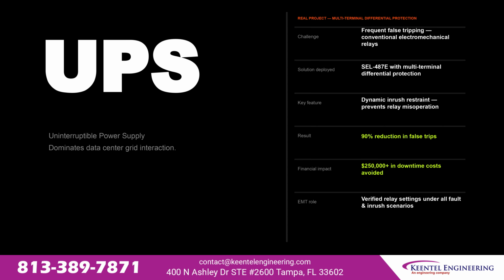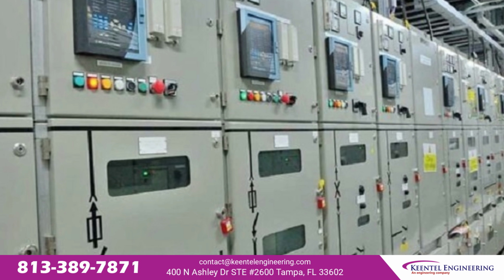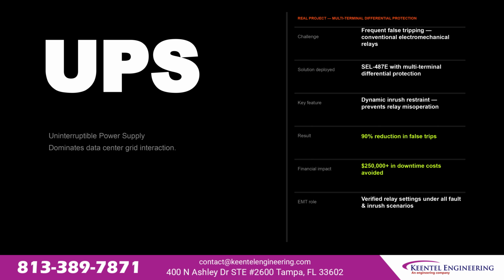SEL487E with multi-terminal differential protection. Key feature, dynamic inrush restraint that prevents relay misoperation during normal switching events. Result, 90% reduction in false trips. Financial impact, over $250,000 in avoided downtime costs. EMT role, verified relay settings under all fault and inrush scenarios before commissioning.